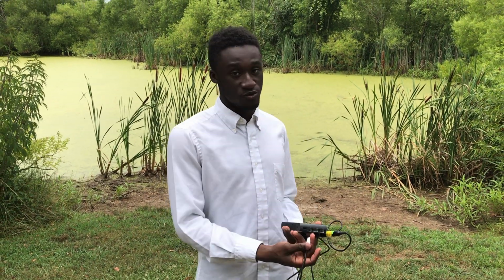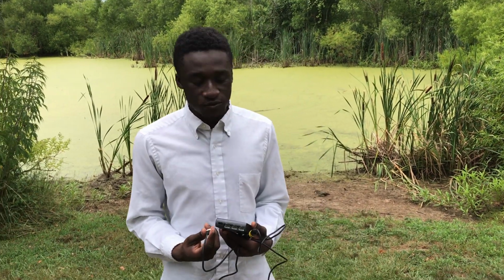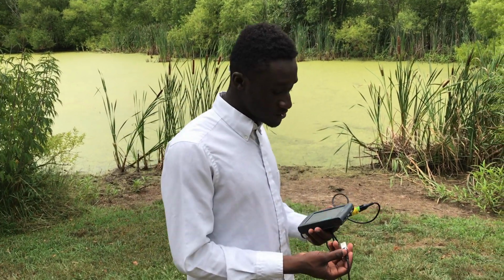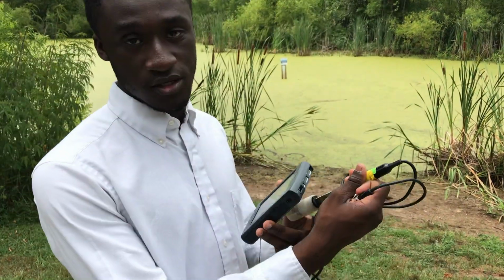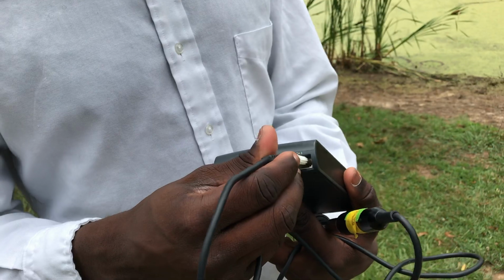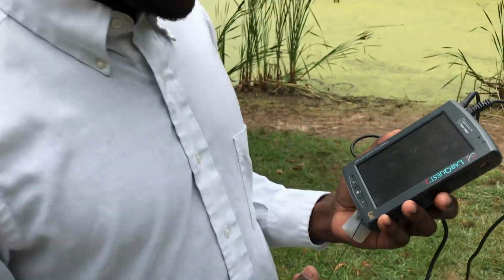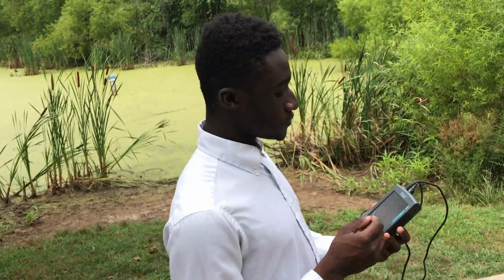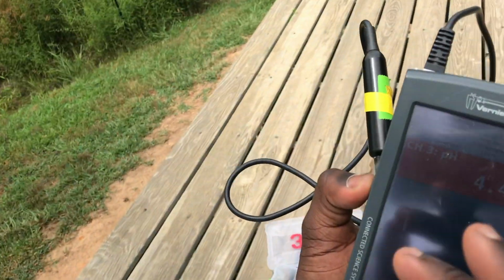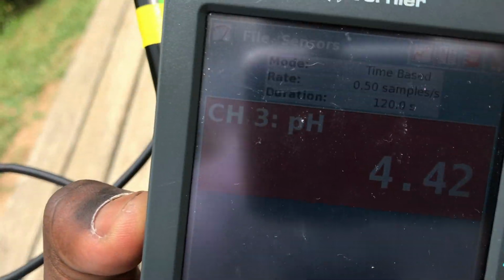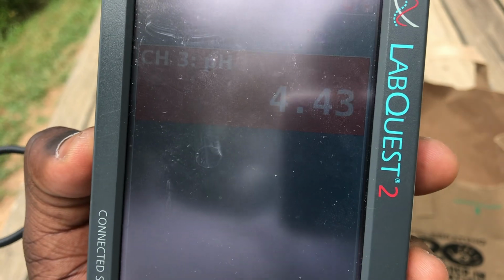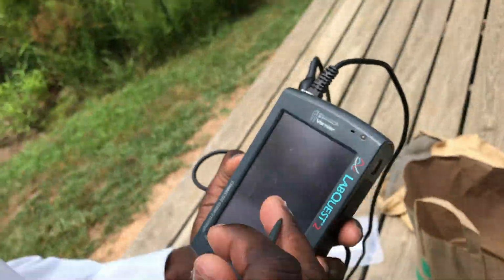And so we'll go through a lot of the same steps as the nitrate calibration, except this time we get to do 1-point calibration instead of 2-point calibration. So we'll take you through the steps of that because it's a little bit different. So we'll get our LabQuest as well as our probe here, and we'll plug it into one of the channel ports as usual. There we go. And we'll immediately get a reading. So this reading, as we can see, is fluctuating pretty significantly. It's going anywhere from 4.35 to 4.4 to 4.3 and then 4.4. And so it's fluctuating a lot because we know that it's not very calibrated.